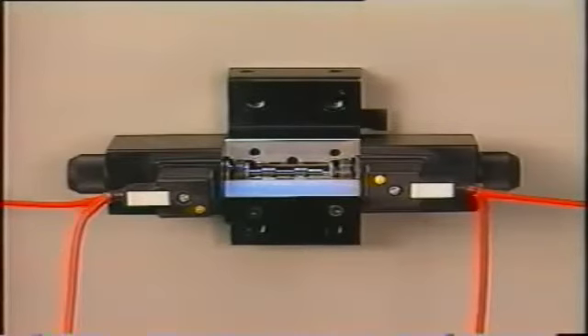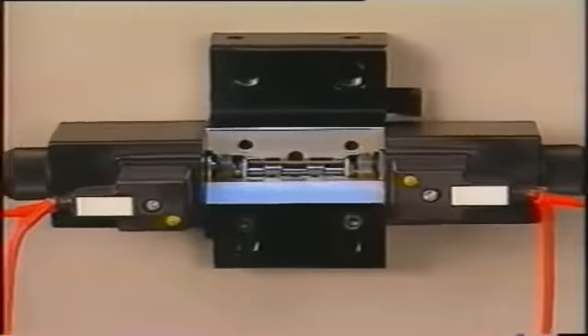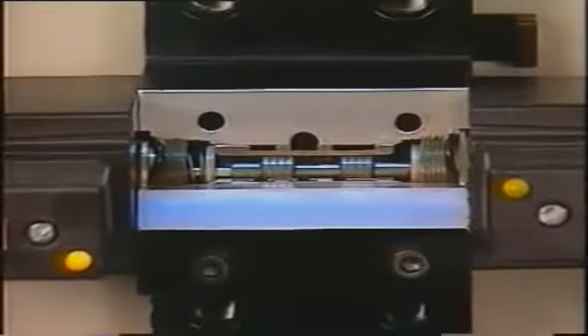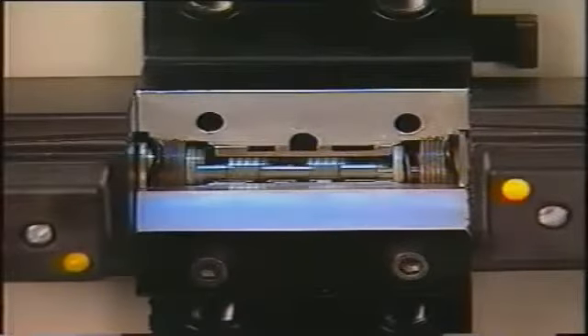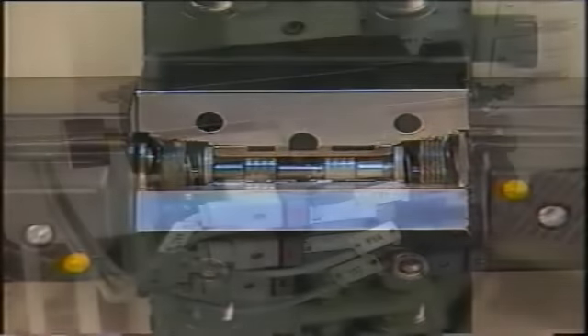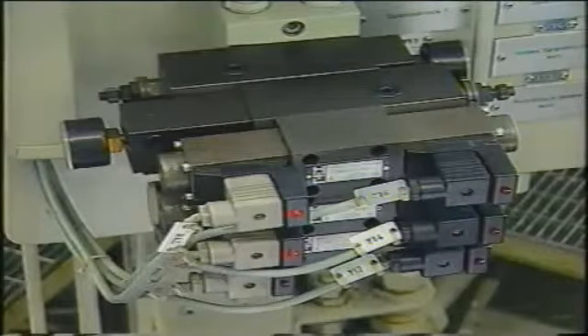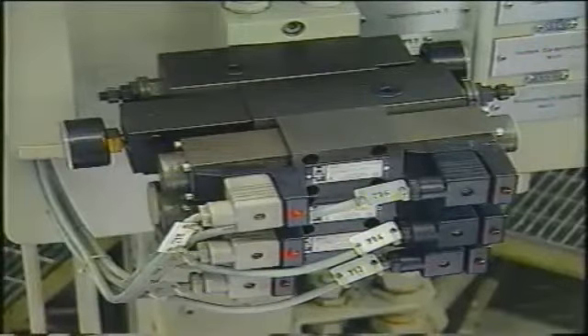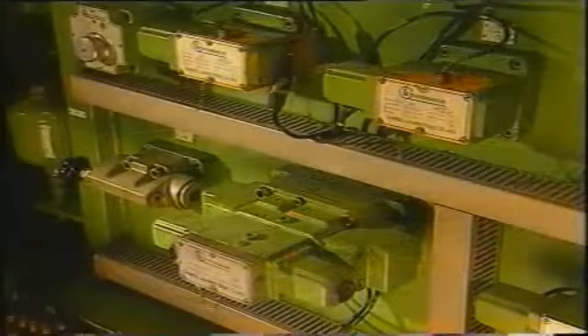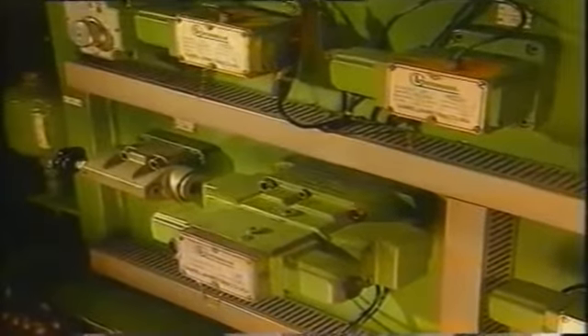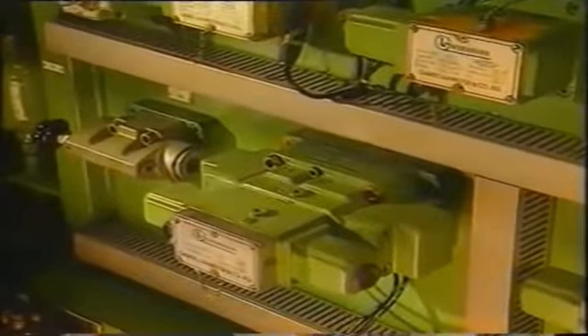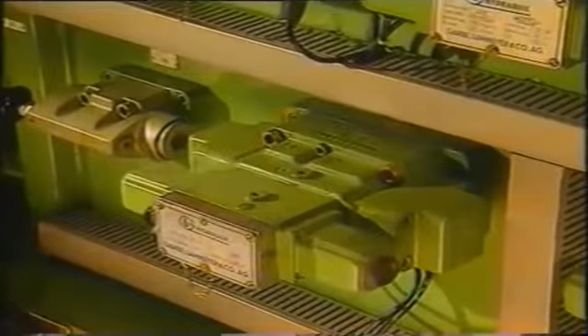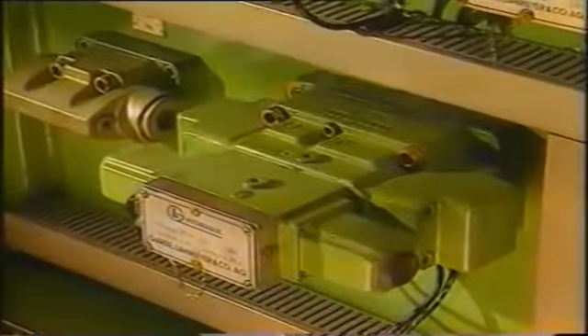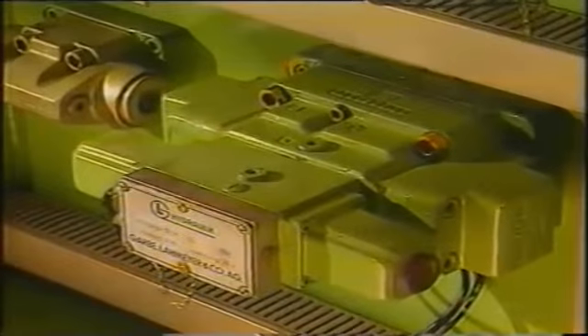Switching of directional control valves means overcoming spring forces, friction, lateral forces and seating thrust. This requires solenoids with sufficient power. And to ensure safe functioning of the solenoid, the heat generated by the coil has to be limited. The solution: the solenoids used are kept as small as possible. In order to nonetheless achieve the required force for switching large directional control valves, the energy of the compressed air or hydraulic oil is used to switch the valve. This process is called pilot control.